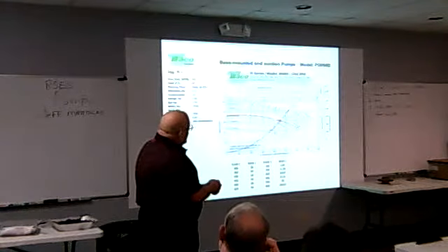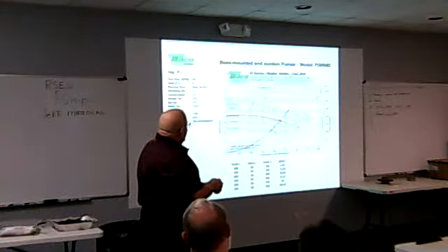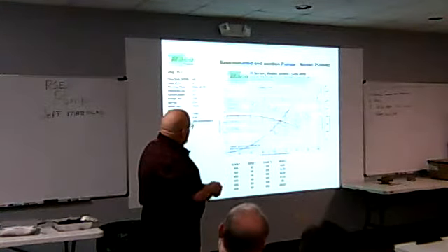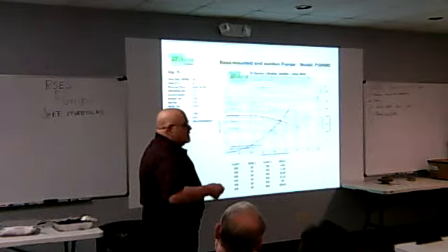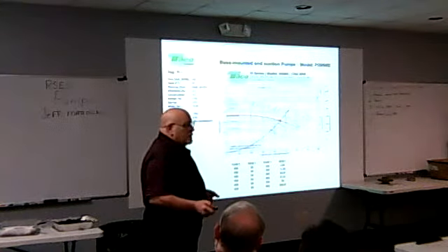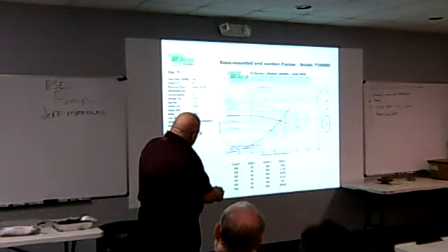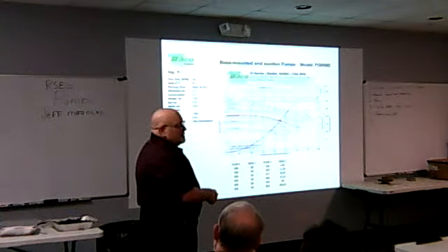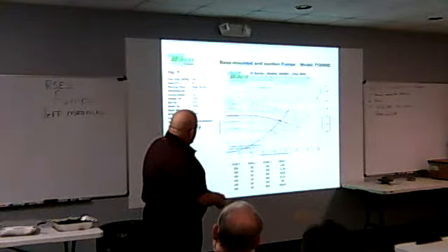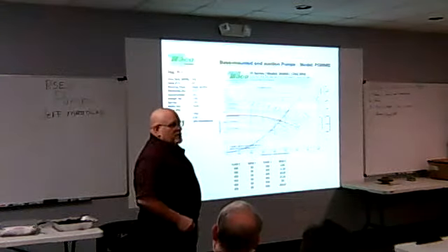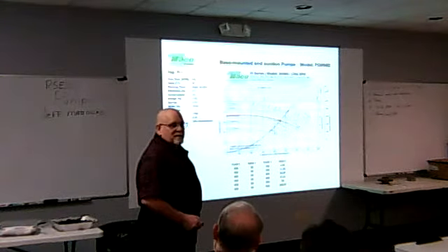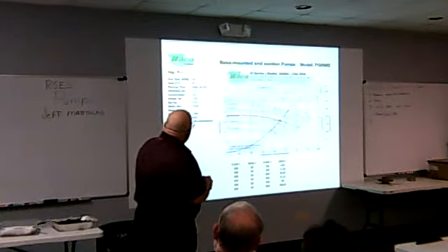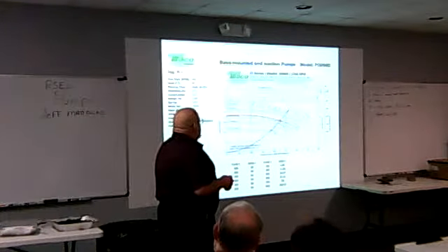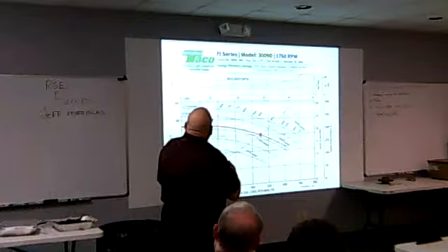If this is a true point of my system, my pump can't go anywhere but here. It has to be on that curve. The head varies as a square of the flow. If I'm at 100 GPM, I'm gonna have 2.96 resistance. If I'm at 600, I've got 106 feet of resistance. Okay, make sense? So that's where the system curves come from.